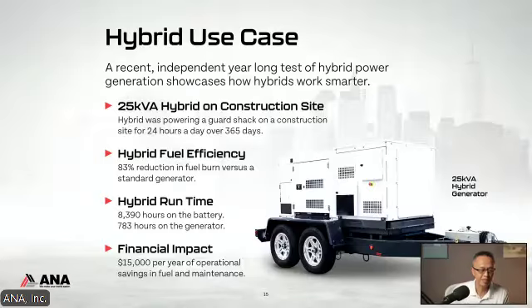Here, by replacing with a hybrid system, the fuel efficiency increased dramatically. We saw an 83% reduction in fuel burn versus a standard generator. And in this case, the generator ran only 783 hours.